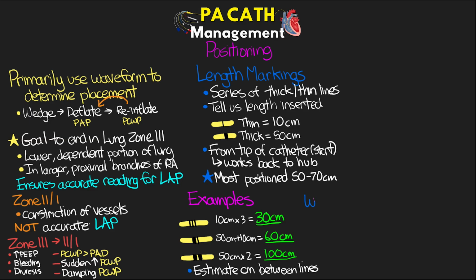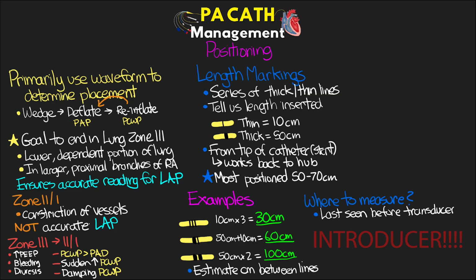Now, I've actually heard of people measuring the swan at a couple different locations. We can measure it at the last point that you can see it before it enters into the introducer, and then there's other people who will also measure it at the point at which it is inserted into the skin. Now, make sure that you're following the proper protocol at your facility, but really we should be going at the last place that we can actually read and see the reading instead of making, sometimes it's almost another 5 to 10 centimeters from where it goes into the sheath until where the insertion site is, and so you're making a big estimate if you're using that as your measuring point.